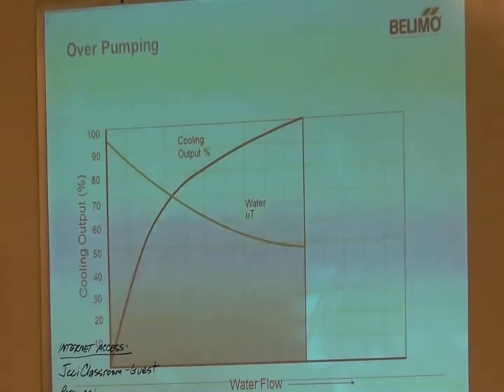Overpumping. So we've been talking that, with pressure-dependent valves, you're susceptible to overpumping. Well, what's that going to do? Well, you can see here our coil characteristic, our valve characteristic, and then your delta T. You can see your delta T is coming down, as we talked about, as your flow increases.